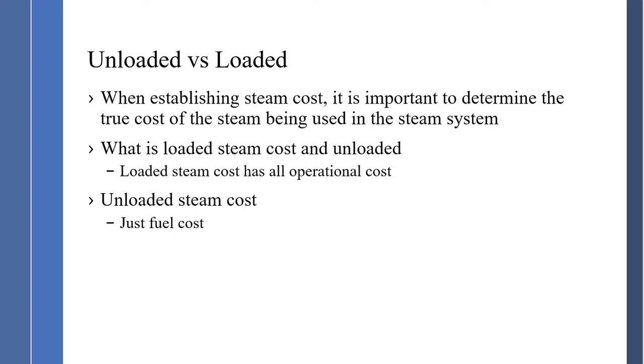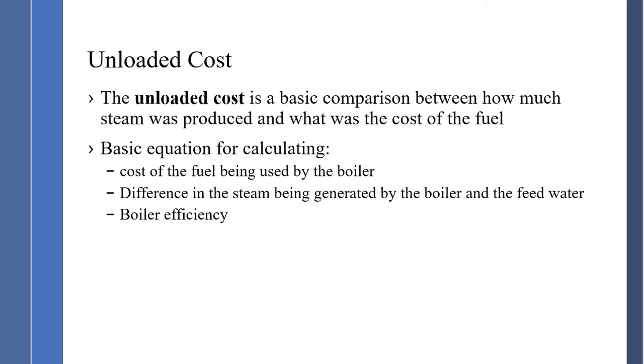Unloaded versus loaded steam costs. When establishing steam costs, it's important to determine the true cost of steam being used in the system. Loaded steam costs have all operational costs: utilities, operations, capital purchasing, administration, etc. Unloaded costs are just the fuel costs used for boiler operation — a basic comparison between how much steam we produce and the cost of the fuel we are purchasing.